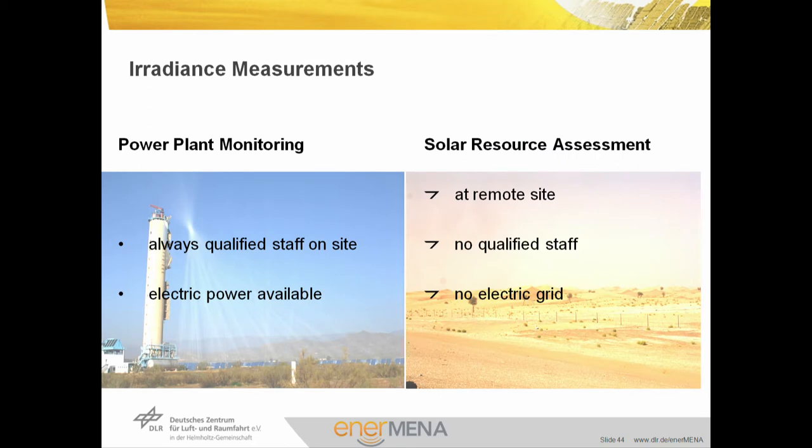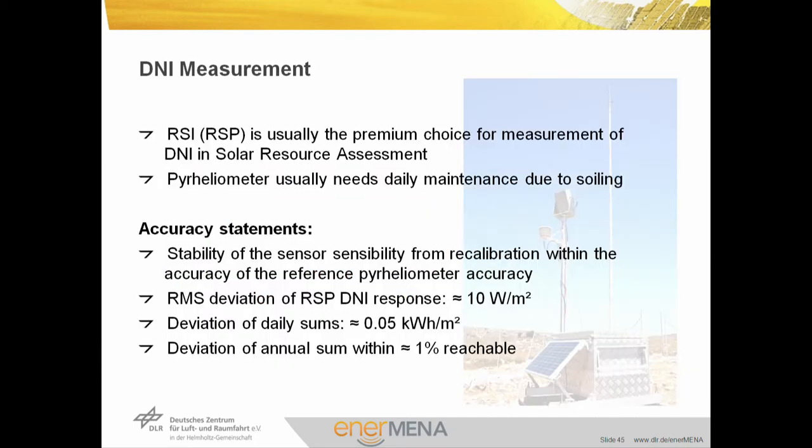We also need to measure the irradiance — the amount of sun that comes onto our solar field. We have different measurement technologies: the high-performance measurement requiring qualified staff on site and electric power, or the solar resource assessment with remote stations. For remote systems, we use rotating shadow-band pyranometers (RSP) as the premium choice for measurement of DNI in resource assessment. Pyrheliometers are used for precise measurement under monitored conditions. The stability is high — the root-mean-square deviation of sensor signal is below 10 watts per square meter, deviation of daily sums is below 0.05 kilowatt-hours per square meter — and in the annual sum we can reach, even with rotating shadow-band pyrheliometers, below 1% uncertainty.